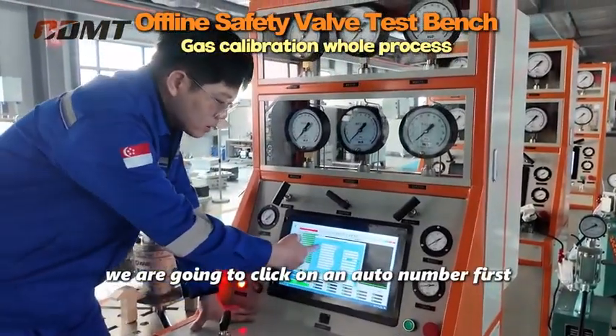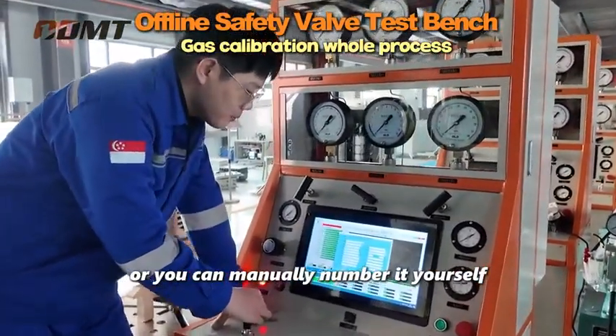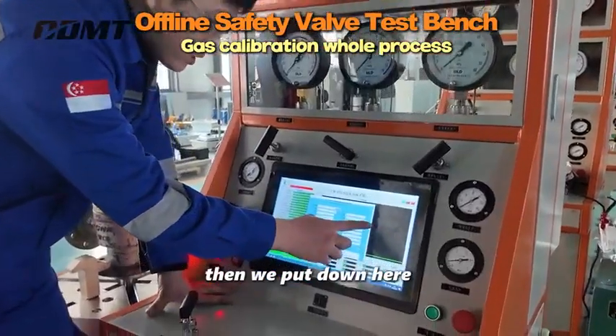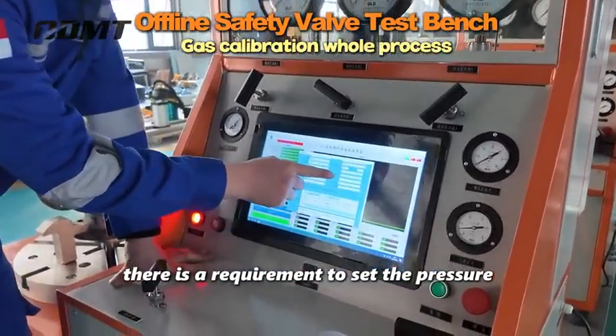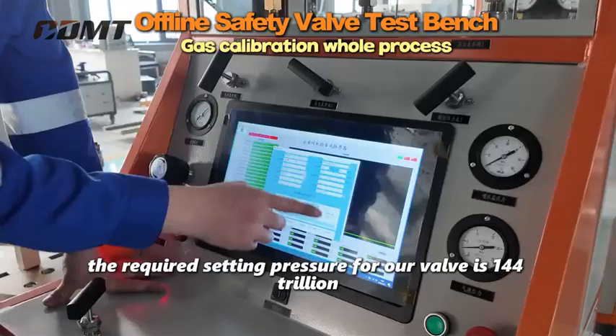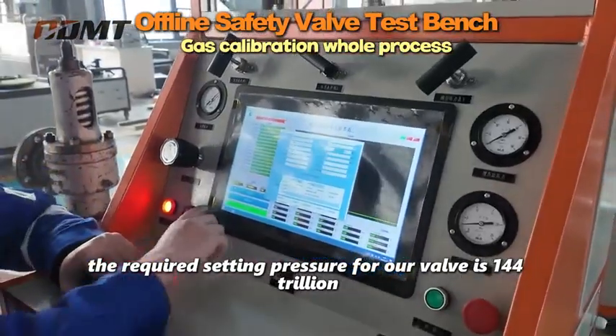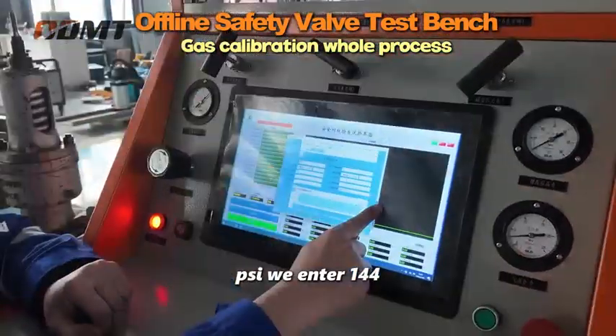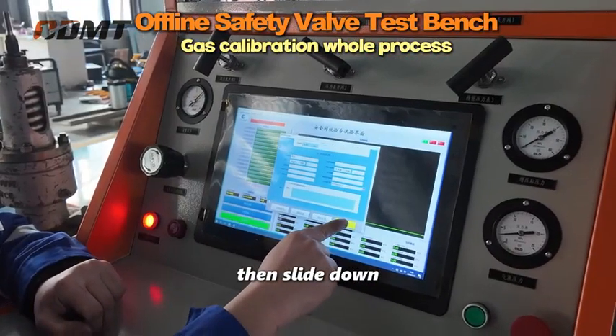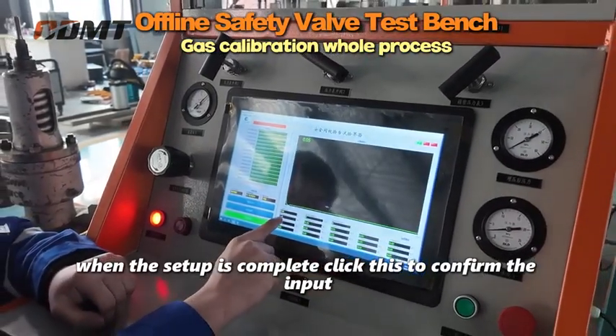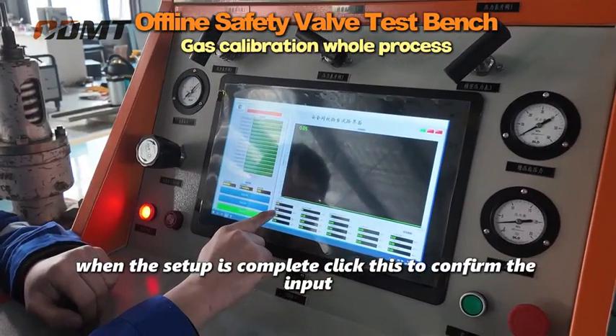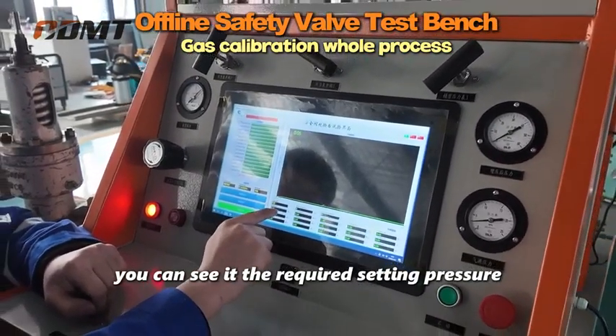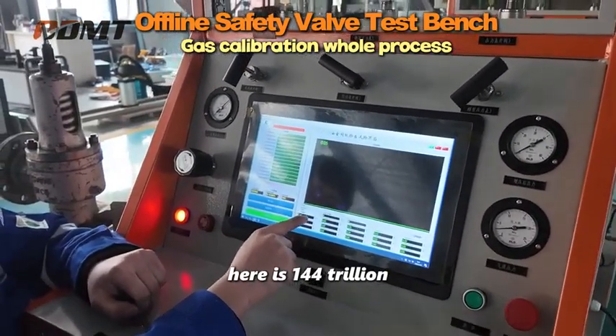We are going to click on an auto number first, or you can number it manually yourself. Then we come down here. There is a requirement to set the pressure. The required setting pressure for our valve is 1.44 MPa. We enter 1.44, then slide down when the setup is complete. Click this to confirm the input. You can see the required setting pressure here is 1.44 MPa.